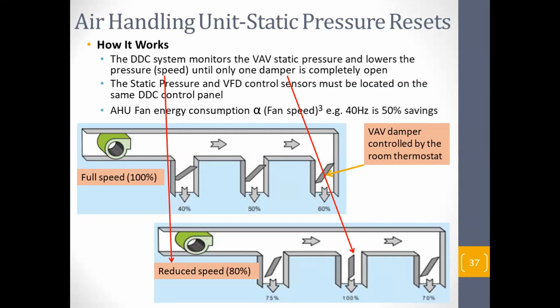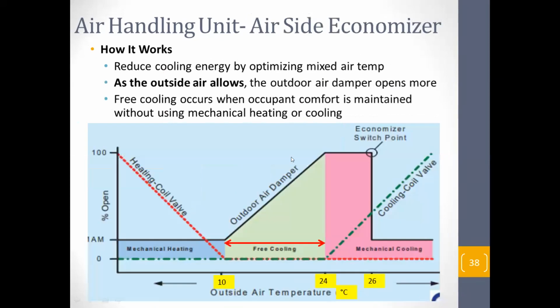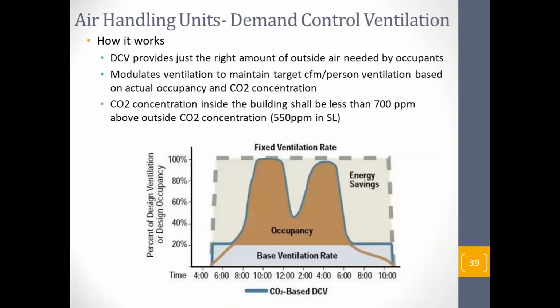If you can monitor the VAVs directly, monitor the VAV which is mostly open and try to maintain that. Whenever a VAV opens 100%, your system will give more air. Whenever the VAVs start to close down, the system will reduce the speed of the AHU fan. This is called static pressure controlling. This one I will skip because it is not very relevant to Sri Lanka.